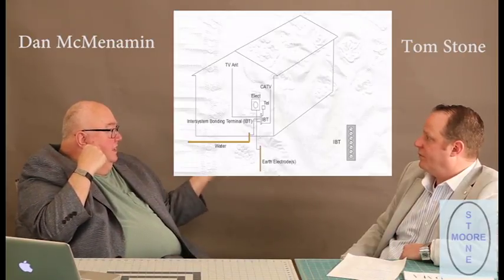Okay. All right, so that connects to that same ground source as the electric field. And so in a well-designed home, everything that's coming in from outside bonds together at one point and then goes to ground. It's called an inter-system bonding terminal in the National Electrical Code. But basically, it's just a bunch of lugs in a bar and going to ground, so that all these things are bonded together, so that you don't have a great difference in potential between any of these devices out in the home.